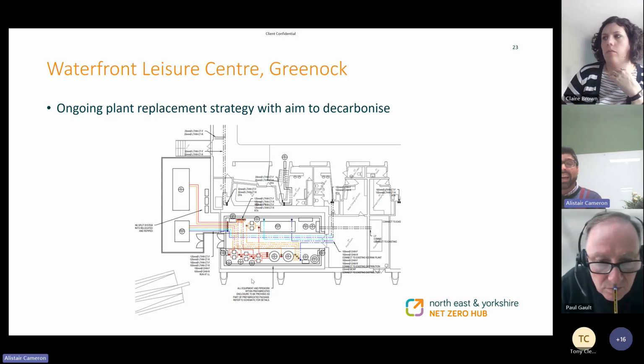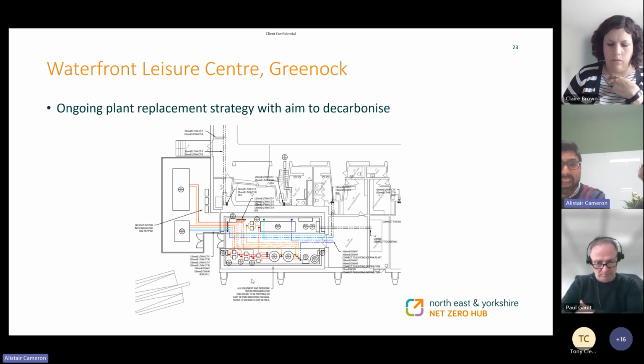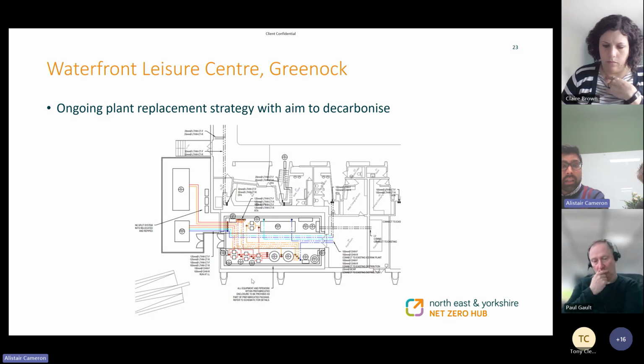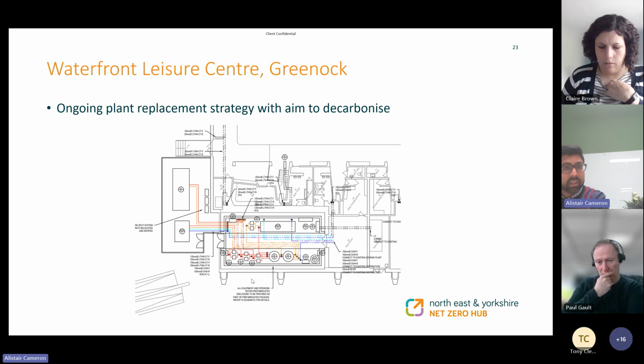And one of the issues they had was the chiller plant was reaching end of life and was beginning to fail and was not particularly reliable. So what we're currently doing is looking at replacing the chillers at the leisure centre, which are currently water to air chillers, with water to water chillers. So again, immediately taking advantage of the heat rejection of the chillers.